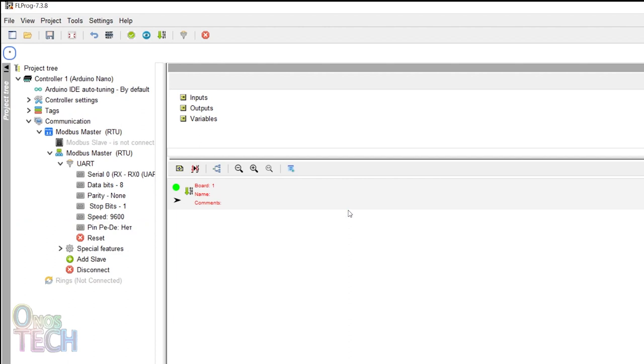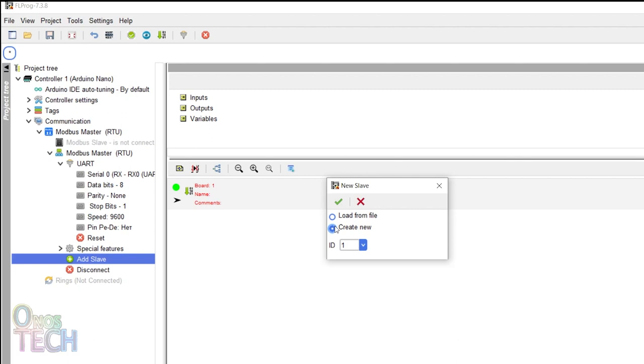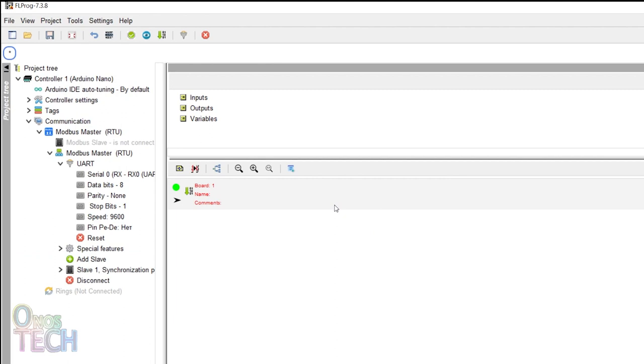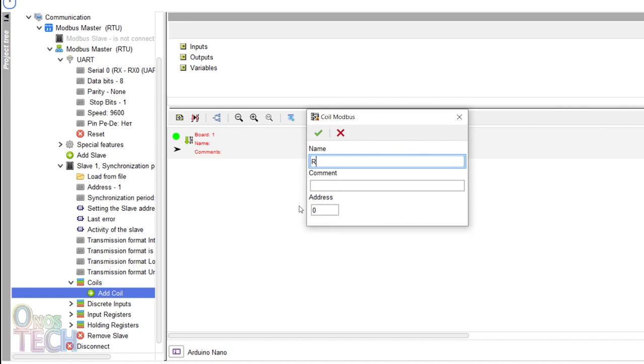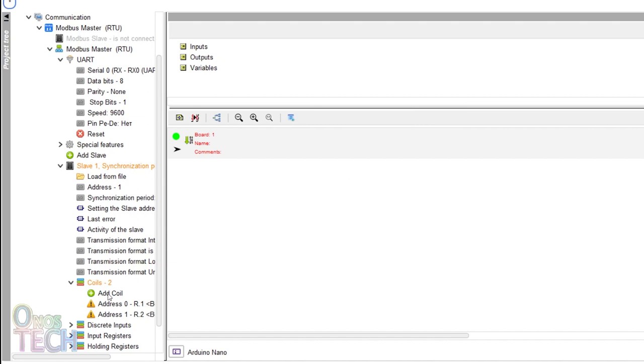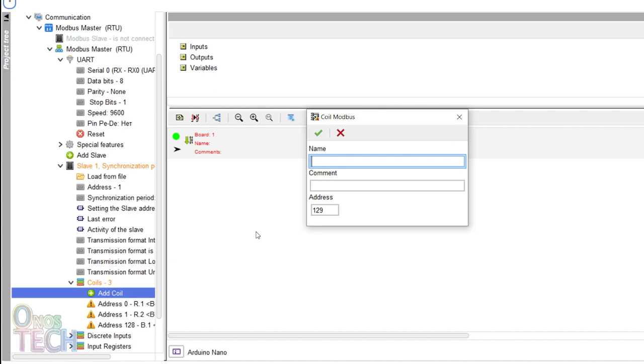To attach a slave device to the master, double-click on Add Slave and create a new slave with a Modbus address of 1. Expand the slave option to display the Modbus register options. Coil tags are created by double-clicking on Add Coil. I will use the ALT PLC output labels and a starting address of 0. Also, create a Coil tag for R.2. Add two more coils for our system memory bits at addresses 128 and 129.